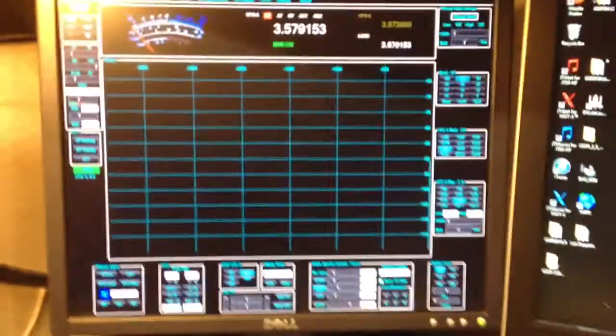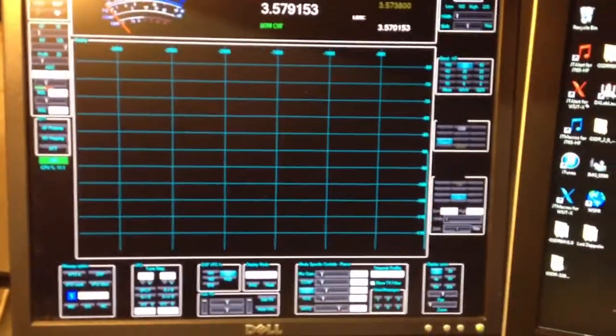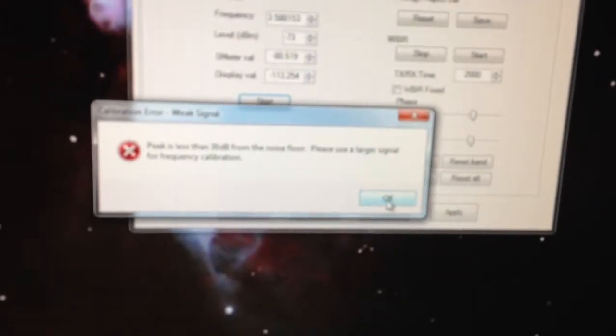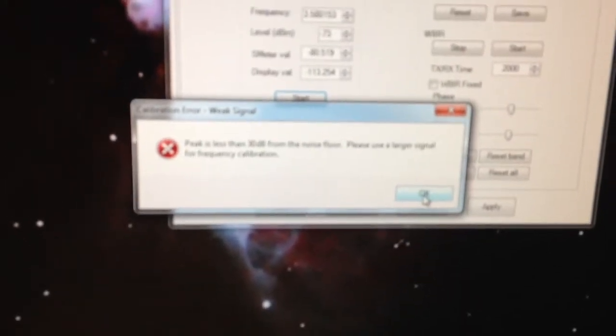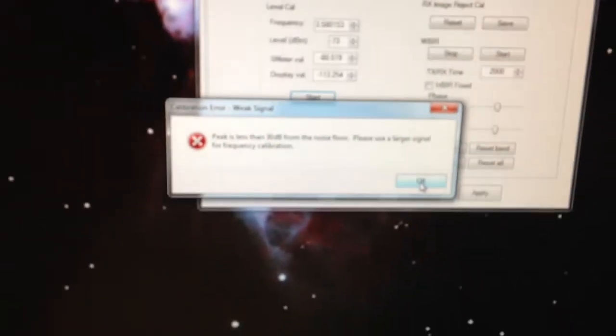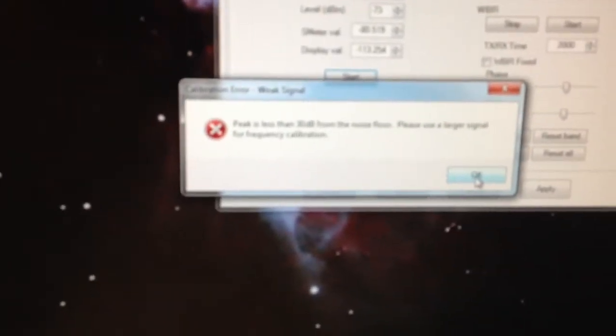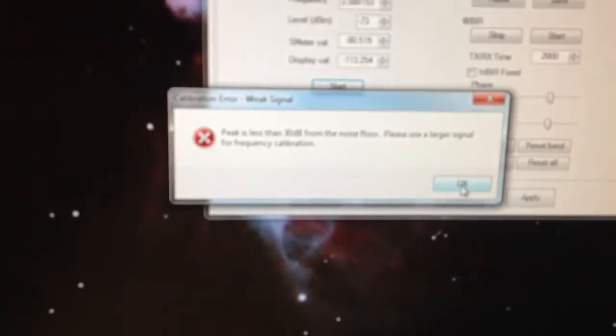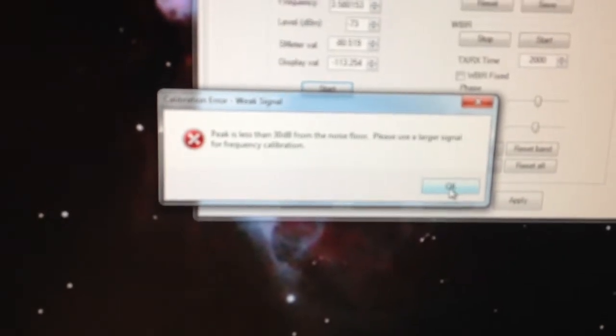And then the software enters the routine. Now, a couple times I've gotten this message box that says peak is less than 30 dB from the noise floor, please use a larger signal for frequency calibration. I find that odd that it refers to it as frequency calibration, because that's not what we're doing—we're calibrating the signal level. So I don't know what to think of that.